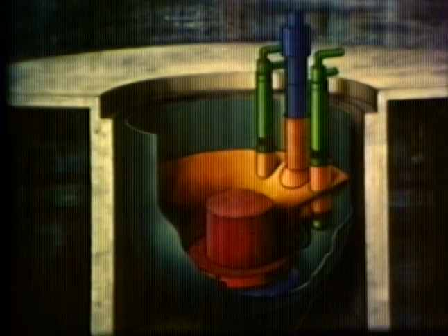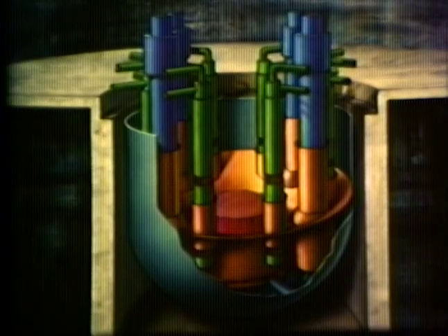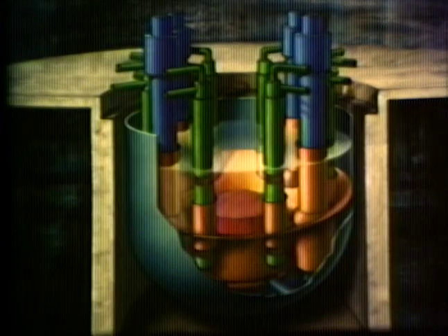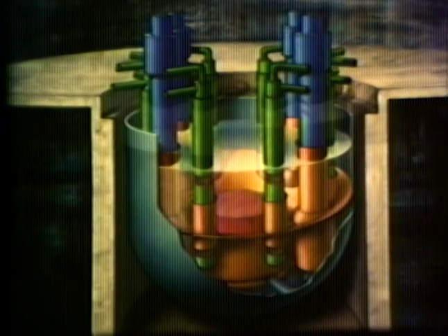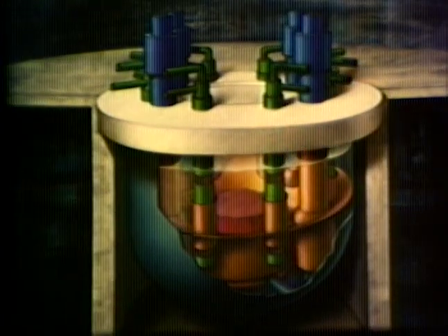At 400 degrees centigrade in the cold collector, and 550 degrees centigrade in the hot collector at the core outlet. All of the primary sodium thus circulates in the main vessel according to this 4 times repeated system, since there are 4 primary pumps and 8 intermediate heat exchangers. This completes the description of the primary system, entirely submerged in liquid sodium and hidden beneath the upper slab inside a solid concrete enclosure.